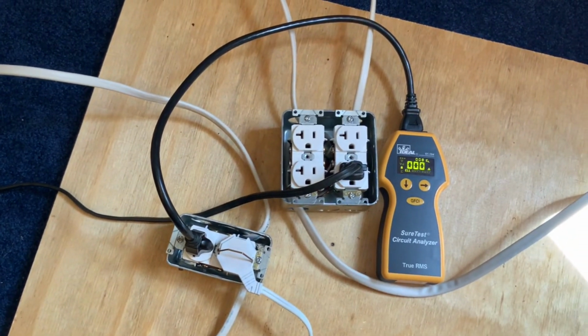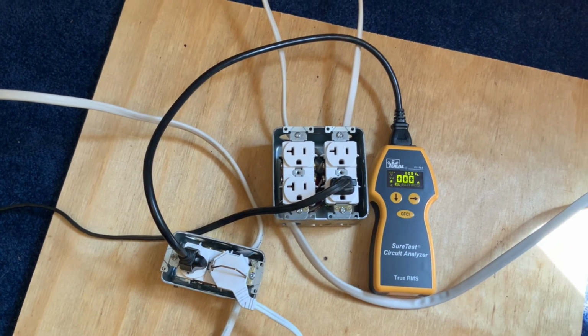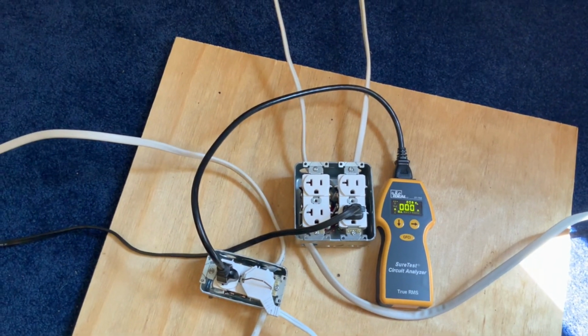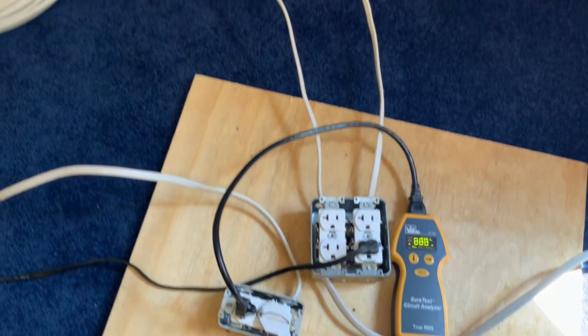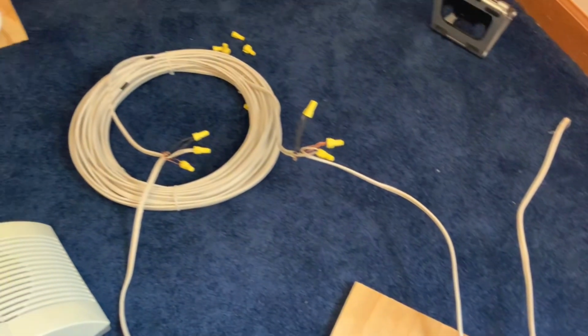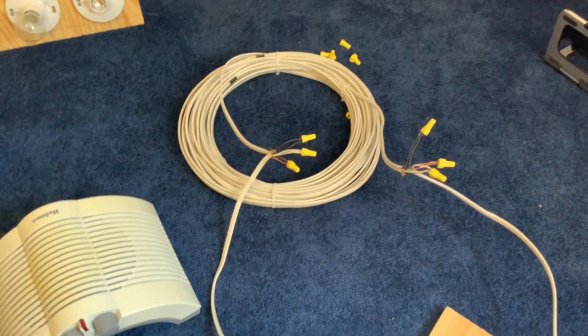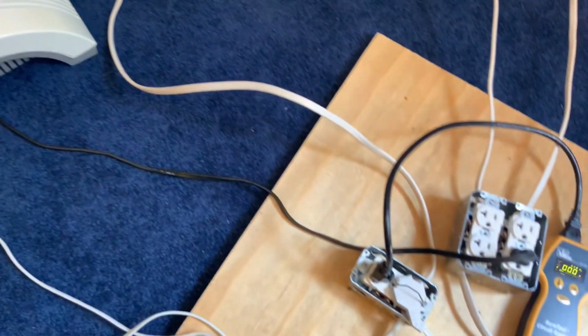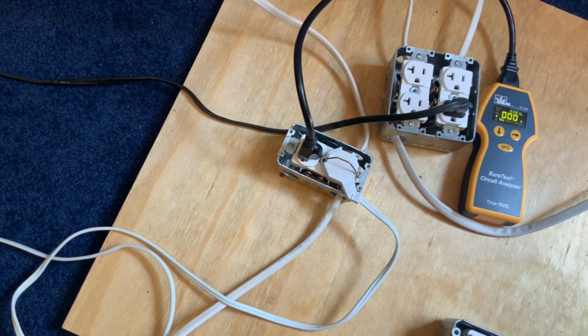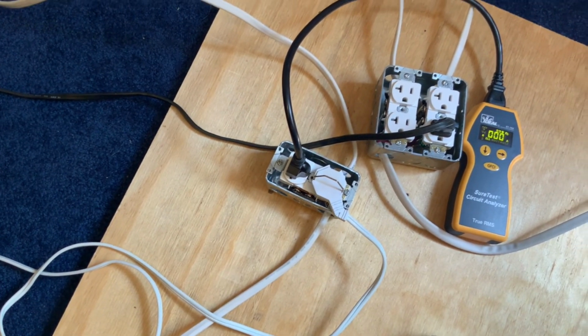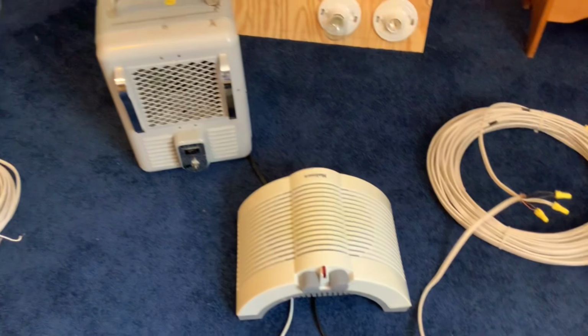And then I'm going to have a heater plugged in on one phase that's on that right outlet there, and then another heater plugged in on that outlet on the bottom after going through the other 90 or so feet of Romex. So these guys are on different phases of the circuit. And you're going to look at what the line voltage drop is as I turn these heaters on.